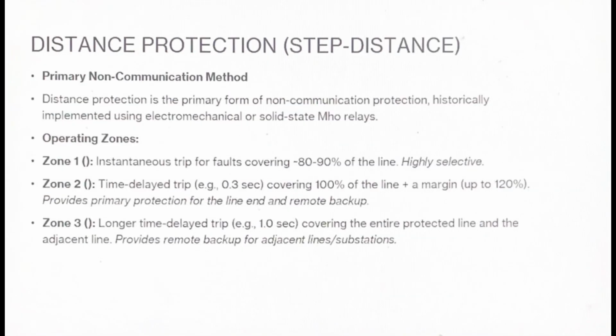For the next slide, it's about distance protection, step distance. The goal is to explain the distance relay operating zones and the basic formula. Distance protection is defined by its operating zones, which are based on the calculated impedance to the fault. The formula is simple: Z equals V over I. So let's move forward to zone 1. This zone covers only a portion of the line, typically 80% to 90%. It trips instantaneously because it underreaches the far end. We know with high certainty that the fault is on our line, making it highly selective and fast.